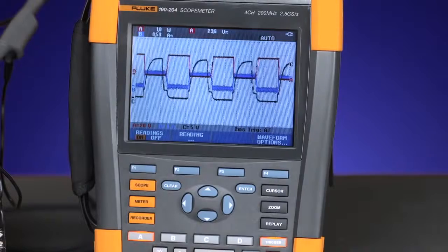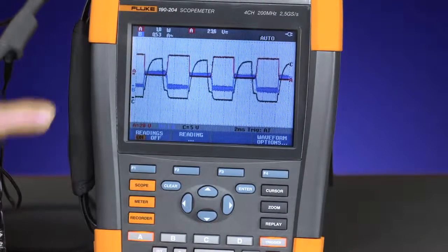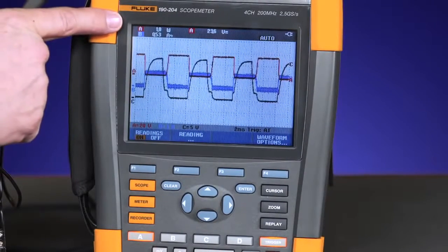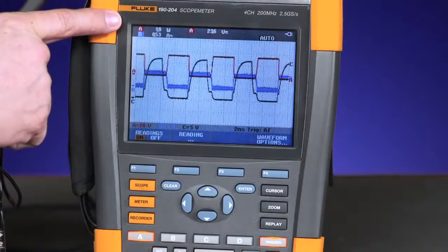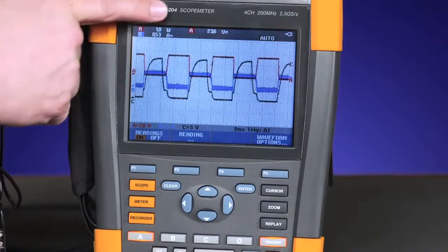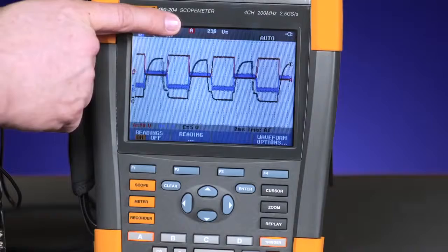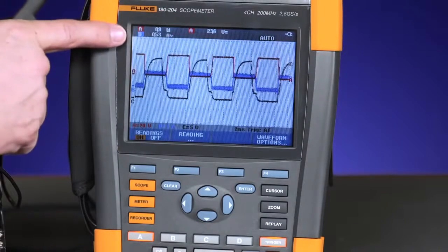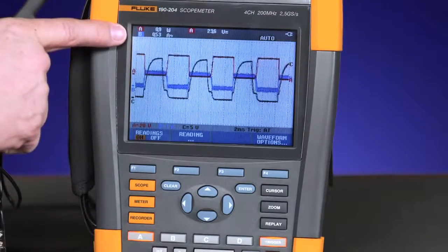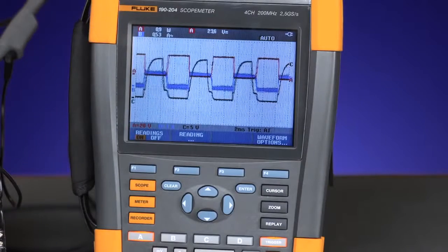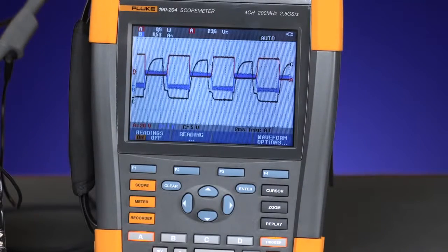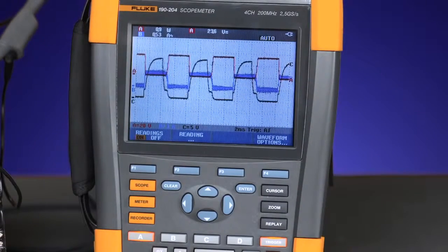What you see on the screen are three independent measurements. Measurement 1 is looking at the power of channel A and B. Measurement 2 is looking at the voltage across the switch. And measurement 3 is of the current through the switch. By looking at those three measurements on that electronic switch, you can now accurately quantify those characteristics and make sure that those values or measurements are within the design characteristics of your system.